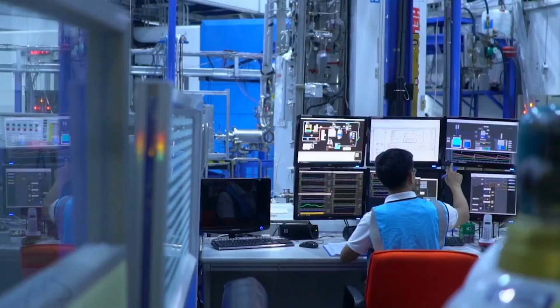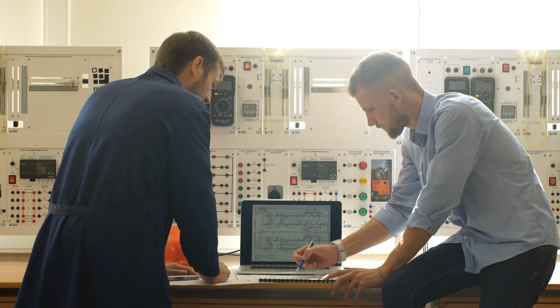Vendor startups must be thoroughly completed to confirm there has been no damage to equipment after shipping and installation, and that equipment is ready for further integration and system testing. Any poorly performed equipment startups will be a weak link in the system and delay commissioning and startup activities.